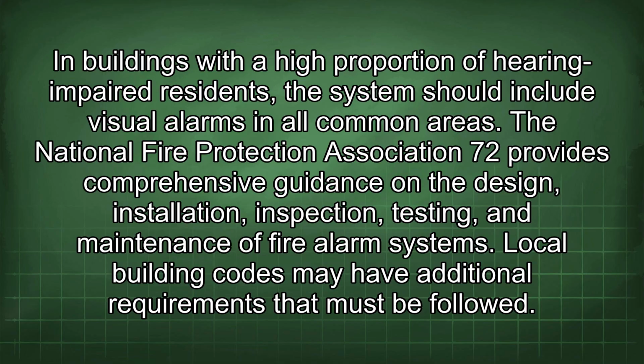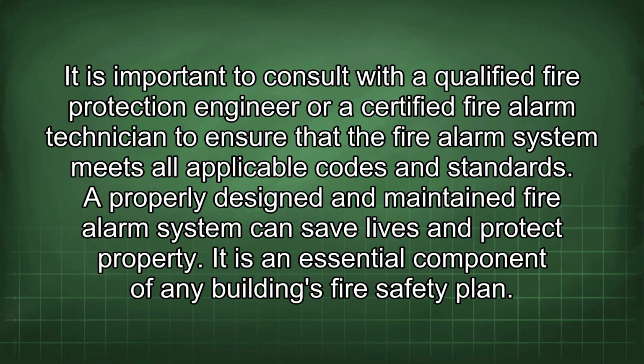In buildings with a high proportion of hearing-impaired residents, the system should include visual alarms in all common areas. The National Fire Protection Association 72 provides comprehensive guidance on the design, installation, inspection, testing, and maintenance of fire alarm systems. Local building codes may have additional requirements that must be followed. It is important to consult with a qualified fire protection engineer or a certified fire alarm technician to ensure that the fire alarm system meets all applicable codes and standards. A properly designed and maintained fire alarm system can save lives and protect property. It is an essential component of any building's fire safety plan.